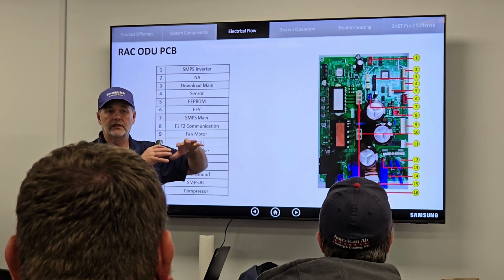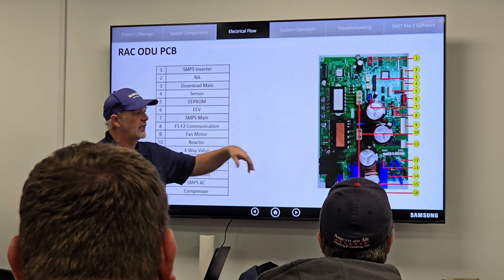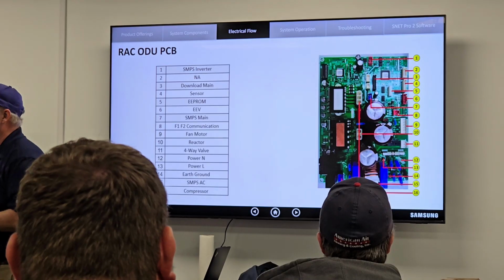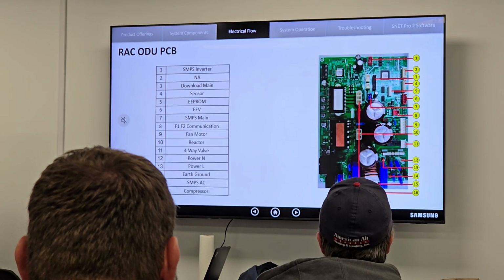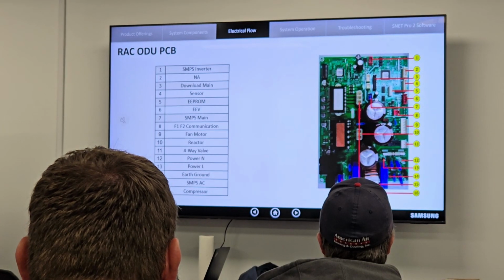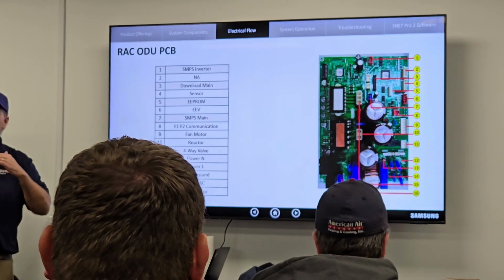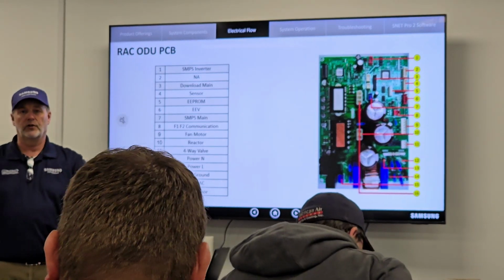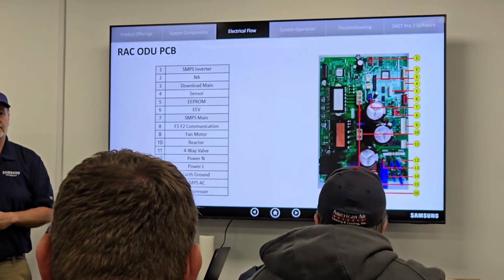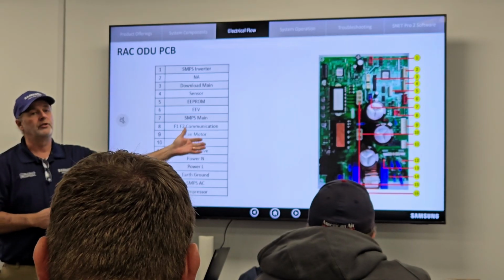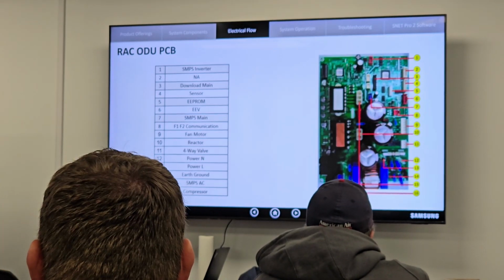That makes sense, they're pitted. So whenever I take that and directly put them onto a heat sink, do I have good contact without grease? No, I don't. I've got some valleys, some pits in there. So that grease evens that playing field up and allows me to transfer heat where it needs to be. So what happens if I don't put grease on a brand new inverter control board?